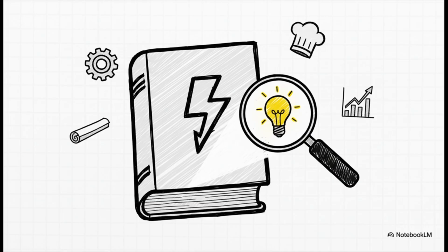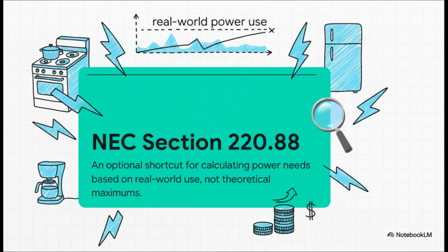And another point in 220.88 clarifies the feeder conductors. What about them? It explicitly says the feeders don't need to have a higher ampacity than the service conductors you calculate using this method. They're sized together based on this optional load. Got it. And you mentioned something critical about the neutral wire calculation before we started recording. That's handled differently. That's right, yeah. Even if you use 220.88 for your main load, calculating the neutral load bounces you back to section 220.61. Why the separate rule for the neutral?